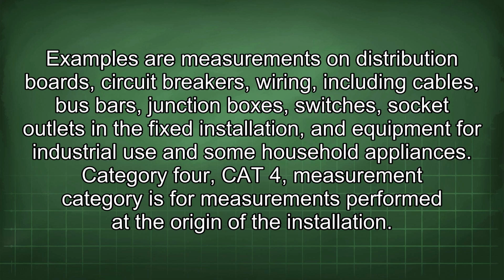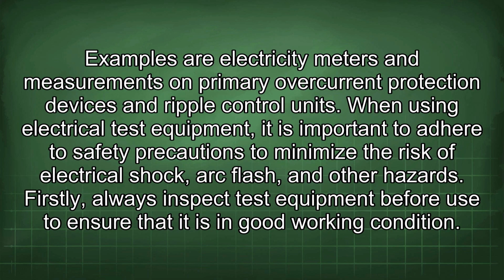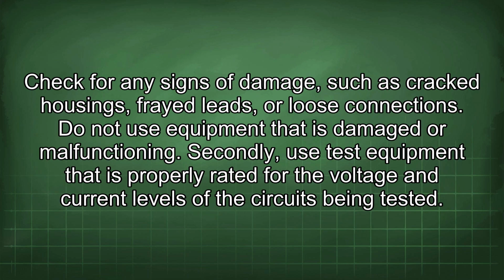Category 4, CAT4, measurement category is for measurements performed at the origin of the installation. Examples are electricity meters and measurements on primary overcurrent protection devices and ripple control units. When using electrical test equipment, it is important to adhere to safety precautions to minimize the risk of electrical shock, arc flash, and other hazards. Firstly, always inspect test equipment before use to ensure that it is in good working condition. Check for any signs of damage, such as cracked housings, frayed leads, or loose connections. Do not use equipment that is damaged or malfunctioning.